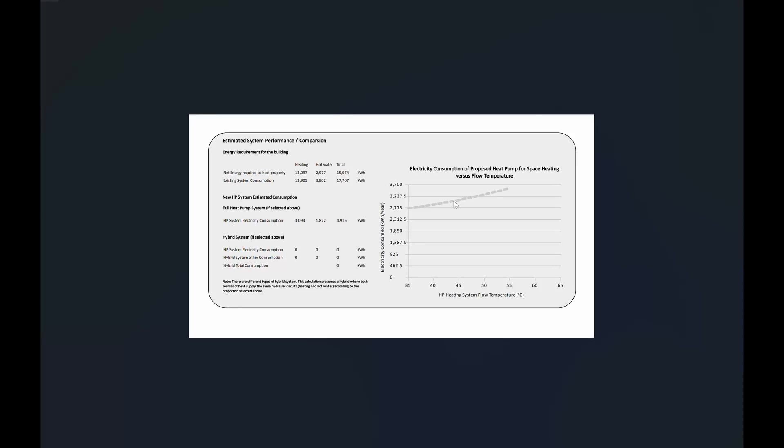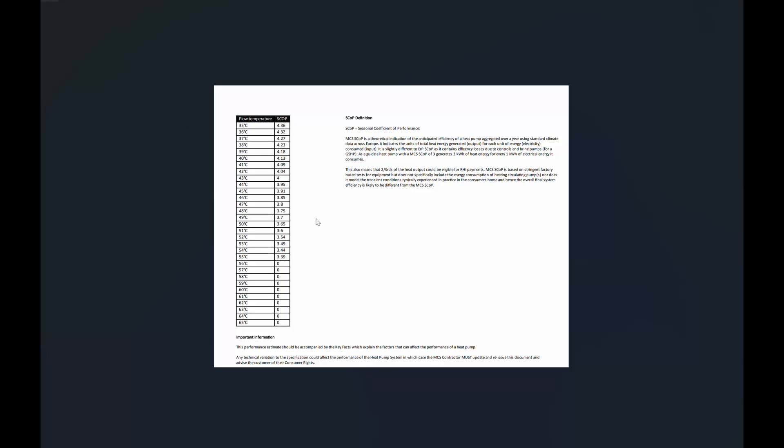Here we can see some of the existing system consumption and the net energy required, and this is based on the 87 percent again so I ignored quite a lot of this to be honest. Here you can see the flow temperature and the amount of electricity consumption that will be required. So we were coming in somewhere around 3,000 kilowatt hours per year was what they were estimating we were going to use for space heating and then domestic hot water. This again is MCS figures that have been submitted and verified to MCS. The reason they use 3.91 is a fixed flow temperature of 45 degrees. Of course we're on weather compensation and so we are regularly 35 degrees or below with a COP of 4.36 which massively improves it.